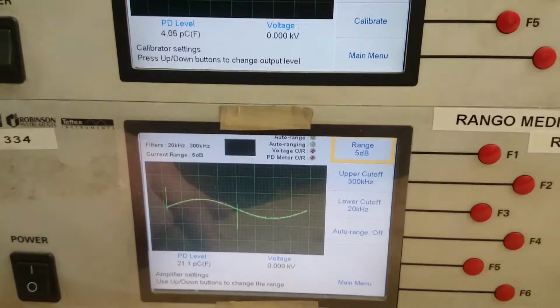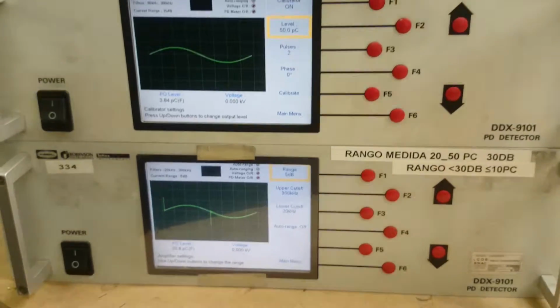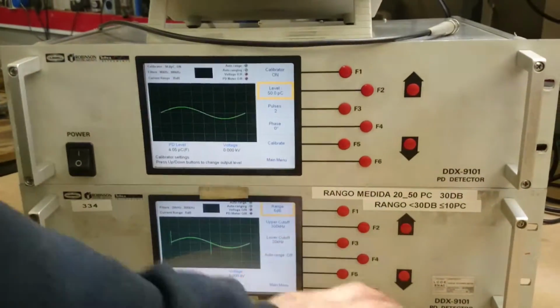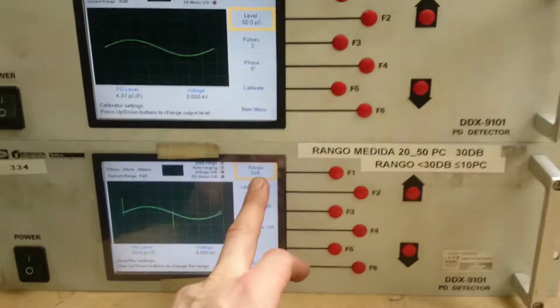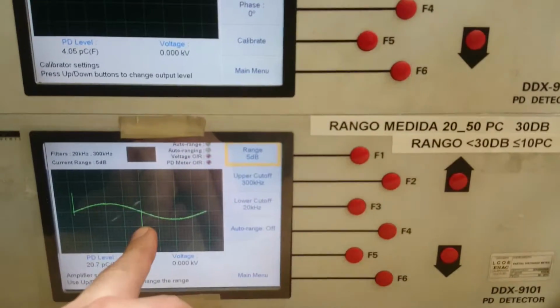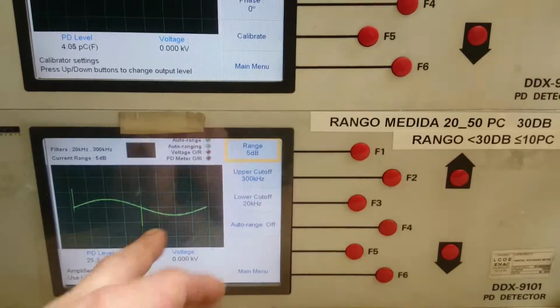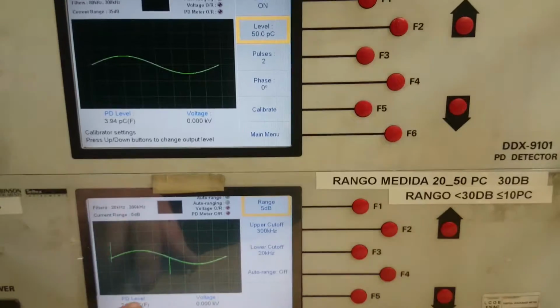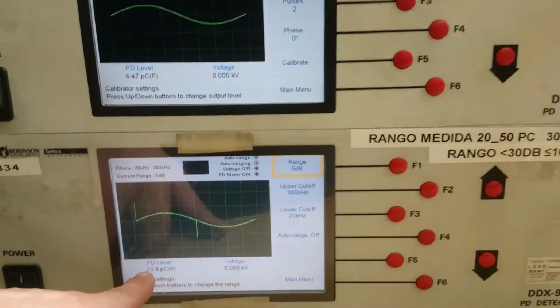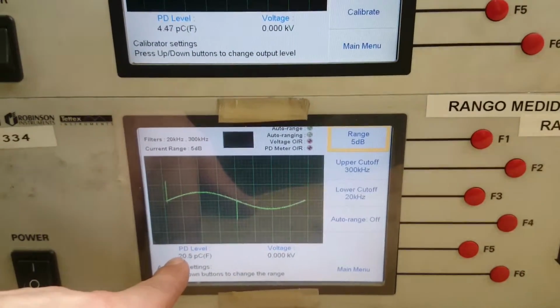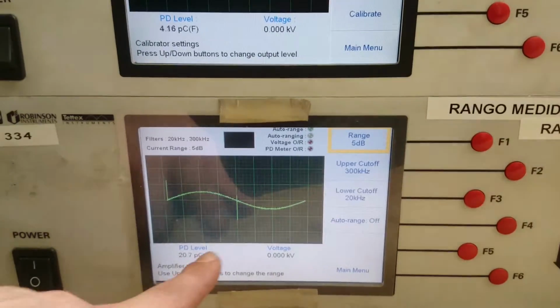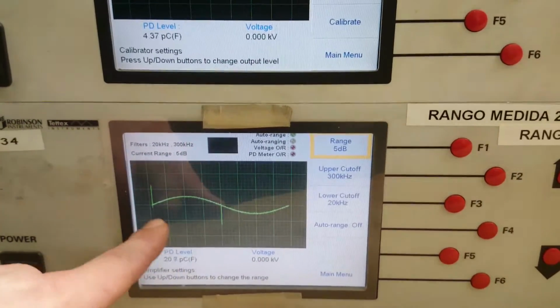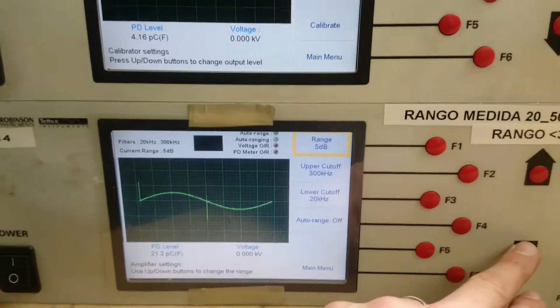So first thing I'm going to check is the ranges are working and that the input attenuators are all good. So we see we're on the 5 dB range now, and the pulses are a nice size. I'm putting in 50 PC, but this is reading 20 PC. So it's not calibrated yet, but before I calibrate, I will just check that the sizes of the pulses change as I change the range.